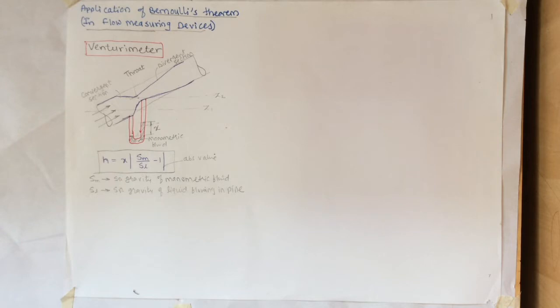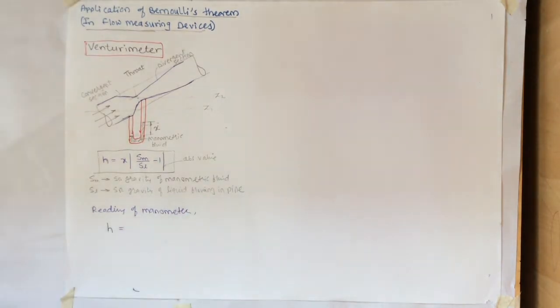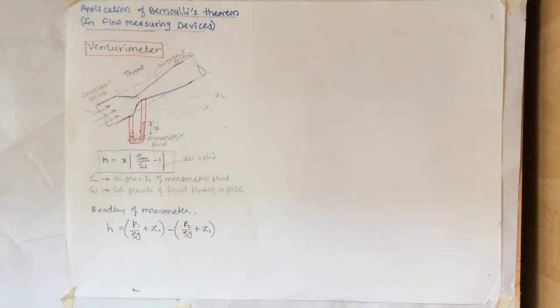Now we can say that this manometer will show you the readings. The manometers are used to read the pressure differences or the pressure head. But here as this Venturi meter is inclined, we get as a reading of manometer H equals P1 by rho g plus Z1 minus bracket P2 by rho g plus Z2. The reading of manometer will give you pressure head difference as well as the datum difference.